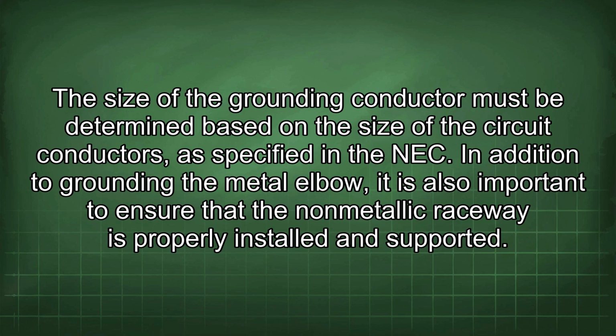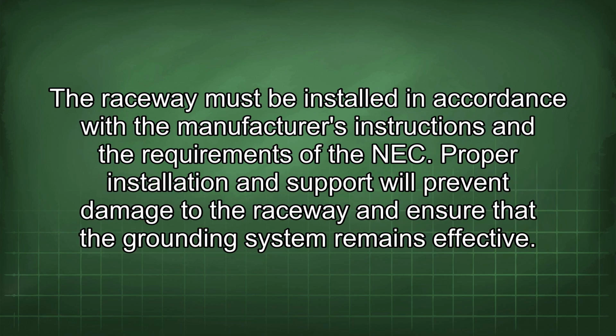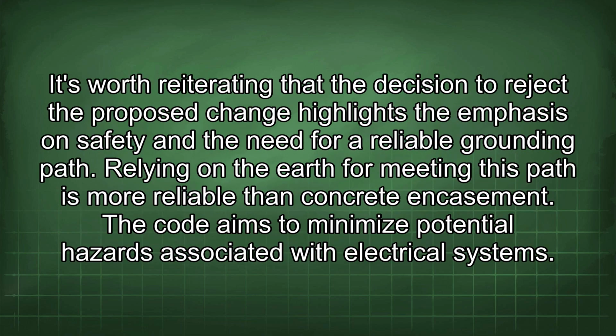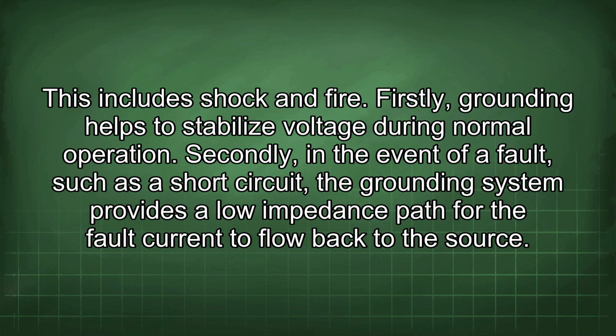The size of the grounding conductor must be determined based on the size of the circuit conductors, as specified in the NEC. In addition to grounding the metal elbow, it is also important to ensure that the non-metallic raceway is properly installed and supported. The raceway must be installed in accordance with the manufacturer's instructions and the requirements of the NEC. Proper installation and support will prevent damage to the raceway and ensure that the grounding system remains effective. It's worth reiterating that the decision to reject the proposed change highlights the emphasis on safety and the need for a reliable grounding path. Relying on the earth for meeting this path is more reliable than concrete encasement. The code aims to minimize potential hazards associated with electrical systems. This includes shock and fire.